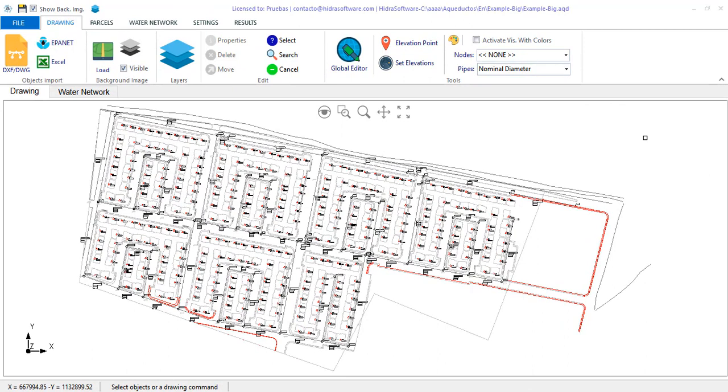Sometimes you will find water distribution networks that must be supplied from two different source points, as could be the case for those that have a water storage tank, floating on the system, and a pumping station. Under this condition, from the point of view of designing the water network, several operating conditions are usually considered, one of which establishes that both the storage tank and the pumping station are simultaneously providing water to the network, and the water consumption corresponds to the maximum.